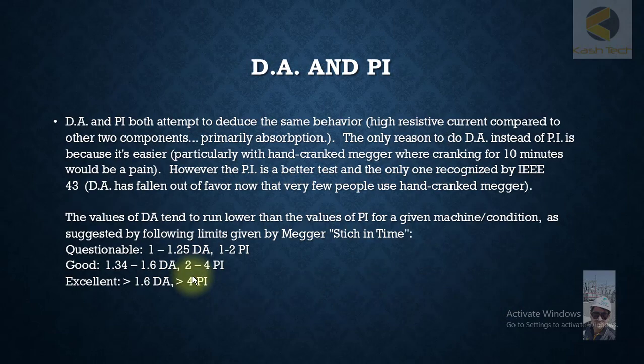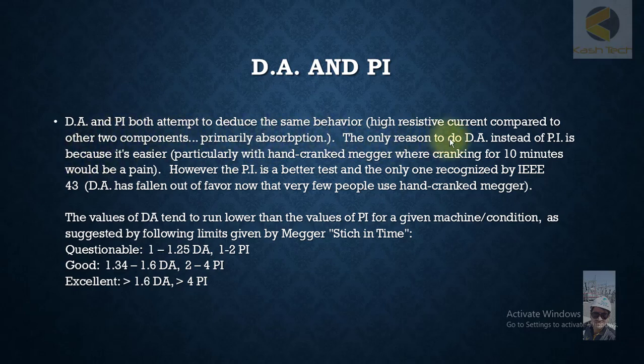Both DA and PI attempt to deduce the same behavior — high-resistance current compared to the other two components, primarily absorption current. The only reason to do DA instead of PI is because it's easier, particularly with a hand crank megger, as cranking for 10 minutes would be painful. However, PI is the better test and the only one recognized by IEEE 43.